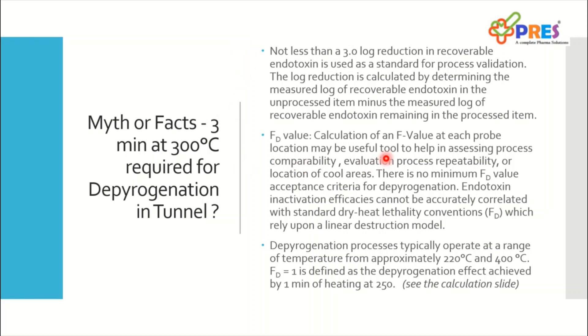Now let's connect to the FD value. Calculation of FD value at each probe — I am talking about penetration probes. Each probe location may be a useful tool to help in assessing process comparability, evaluation of the process, repeatability, or cooling area. The importance of FD value is that we can assess it during periodic or routine requalifications. Based on this physical parameter, we can understand how our process is moving, whether there is any kind of shift or deterioration of our equipment. That's how FD is important.